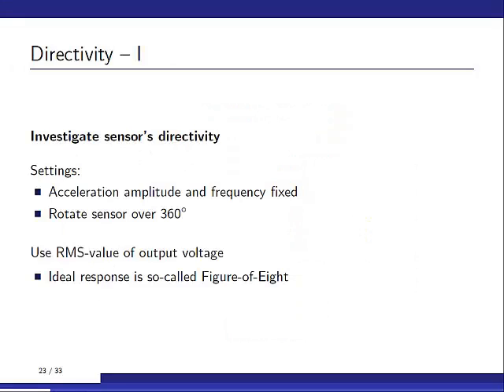We can also look at the sensor directivity, because we said we want to have one degree of freedom for our accelerometer, so the question is, do we really have achieved that? So what we did was, we fixed the amplitude and the frequency of the acceleration, and we rotated the sensor over 360 degrees, and we looked at the RMS output value. And ideally, you would get, you want to achieve, a so-called figure of eight.